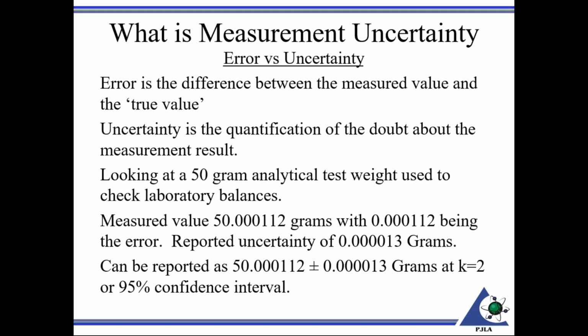Send it out for calibration. It may not be exactly 50 grams. So you could see the actual measured value very close to 50 grams. However, it's 50.000112 grams. Hence, the 0.000112 would be the error. Reported, perhaps, with an uncertainty of 0.000013 grams. So what that means is that the test weight was measured and it was determined that the actual value is, or you can say your correction is, a positive 0.000112, or approximately 1/10 of a milligram, from 50 grams.